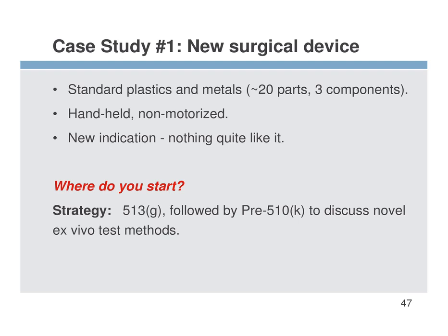a 513G. 513G is named after a section, the 513G section of the Food, Drug, and Cosmetic Act, which says if you're uncertain about your classification of a device or whether it is a device, you can send us in some information and we'll give you an answer back in 60 days. You have to pay for it as well. So it's kind of like a pre-sub, but it's not really within the scope of this meeting. So we got that feedback from them.